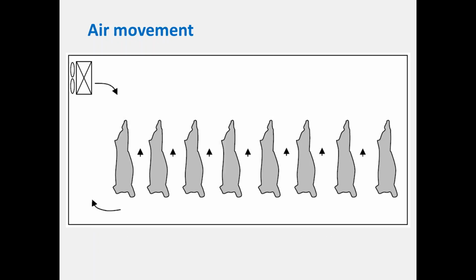Air movement is very important. This is an example of a carcass chiller which just has evaporators in one corner with the fan. One big problem is short-circuiting: you get the air falling down and just circulating around the chiller, around the evaporator, while these other lines are just relying on natural convection. Because the carcasses are warm, you get that upwards flow of air. Ideally, in this situation, a lot of research was done at the Meat Industry Research Institute of New Zealand, where I used to work, trying to promote air movement and air turbulence to distribute air evenly over those carcasses.